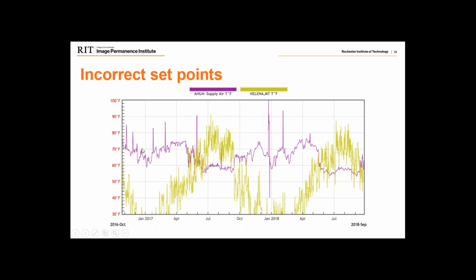For the interior spaces, we're actually running warmer in the wintertime and much cooler in the summertime. While it makes some sense to warm the space more in winter and cool it more in summer, it's actually counterintuitive for energy use. In winter we might make better use of cooler conditions for passive conditioning—if we lower the temperature without changing the dew point, we can raise relative humidity, do less humidification, and provide a cooler, better condition for the space. Consequently, in summertime this becomes a lot of work for the mechanical system.